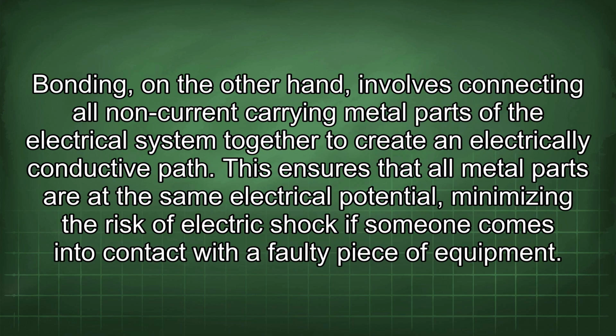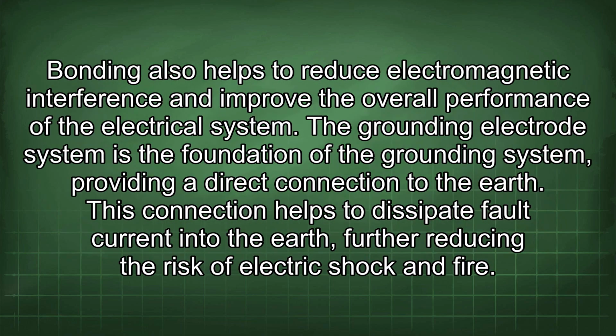Bonding, on the other hand, involves connecting all non-current carrying metal parts of the electrical system together to create an electrically conductive path. This ensures that all metal parts are at the same electrical potential, minimizing the risk of electric shock if someone comes into contact with a faulty piece of equipment. Bonding also helps to reduce electromagnetic interference and improve the overall performance of the electrical system.